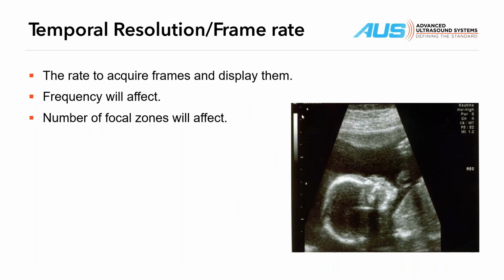Temporal resolution and frame rate. I mentioned frame rate is how quickly the image area itself is refreshed. And it's normally measured in hertz, right? Frequency. And it's normally around 30 hertz, but there are things that can affect that. The number of focal zones in this image particularly, you can see we only have this one focal point here, which tells the system we're focusing in this area of the image. You could add focal points if you wanted, and that would make it clearer in a wider focal area. In other words, more of the image would be focused.